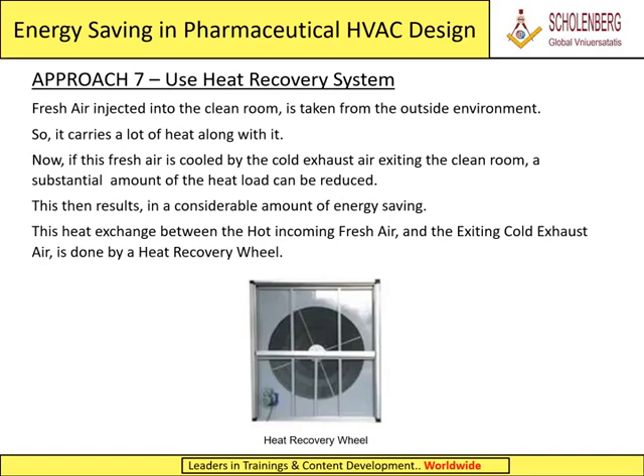Approach 7, Use heat recovery system. Fresh air injected into the clean room is taken from the outside environment. So, it carries a lot of heat along with it. Now, if this fresh air is cooled by the cold exhaust air exiting the clean room, a substantial amount of the heat load can be reduced. This then results in a considerable amount of energy saving. This heat exchange between the hot incoming fresh air and the exiting cold exhaust air is done by a heat recovery wheel.